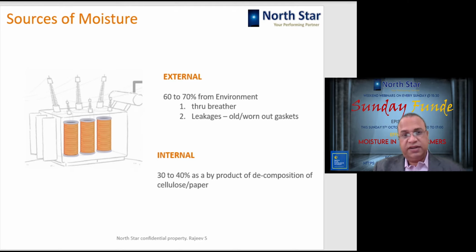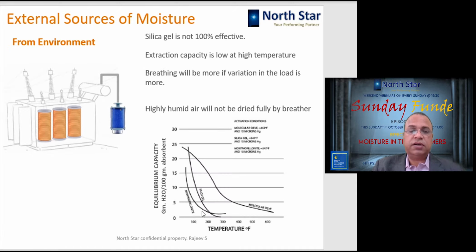The second source is internal, where 30 to 40% of the water inside the transformer gets generated within itself because of decomposition of cellulose paper. So these two sources of moisture affect the transformer in an adverse way. So what does water do to the transformer?